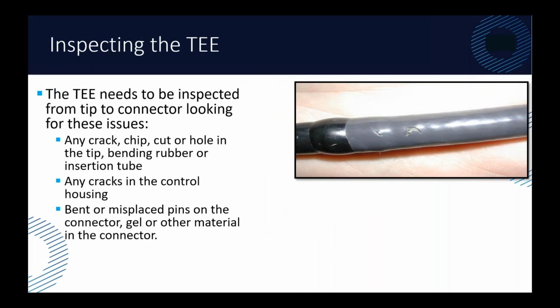Okay, so that's pretty much it with anatomy. Now we're going to get into inspecting the TEE, much like we did with the endoscope. Basically, we want to look for any crack, chip, cut, or hole in the tip, bending rubber, and insertion tube, and any cracks in the control housing, which we probably aren't going to see, but maybe at the strain release. And then the other thing is bent or misplaced pins on the connector. In the endoscope world, connectors are different. But on the TEE side, we see a lot of damage come at the connector. And again, most likely that's happened in central processing.